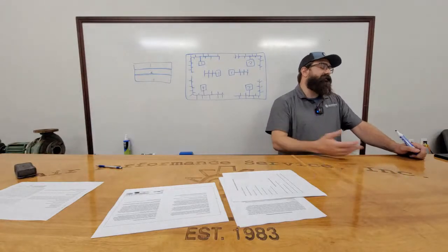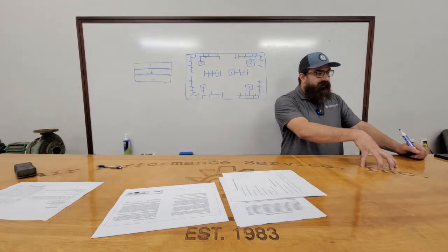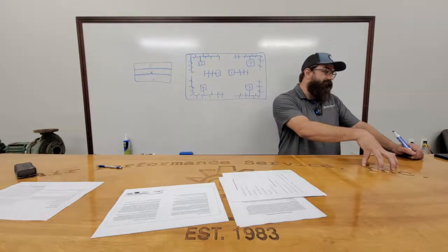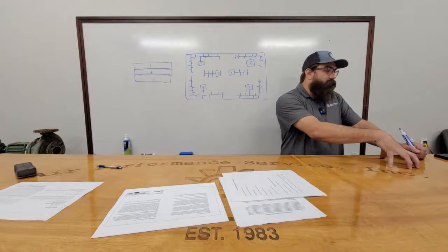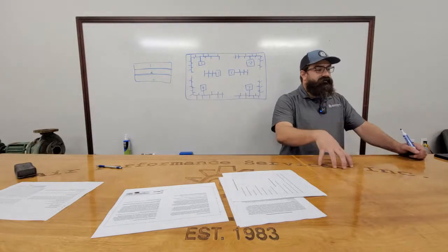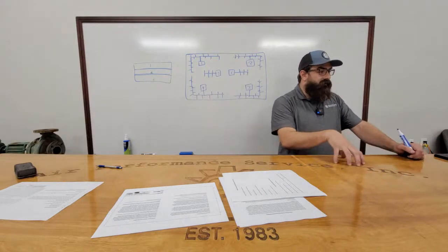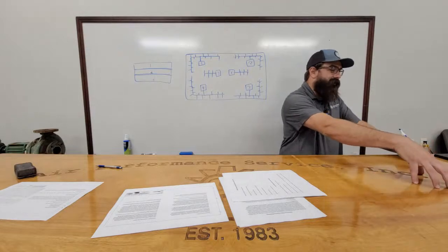So typically, let's just say we're enabling 5 units. Typically you only have 3 that ever start up, but worst case scenario, if all 5 start at once, it never pushes us over. Once they start, that inrush is gone. We can then immediately go to the next group, right?